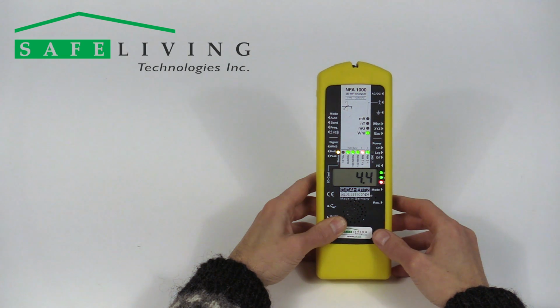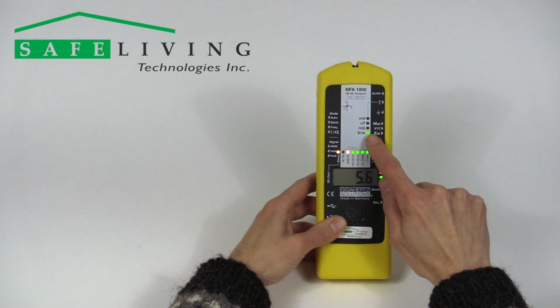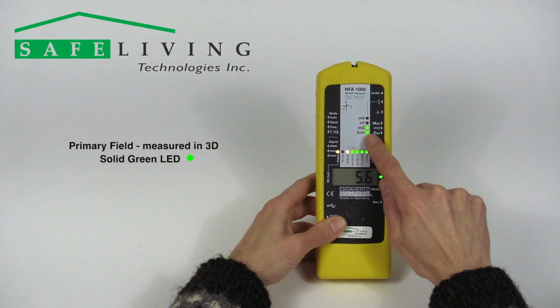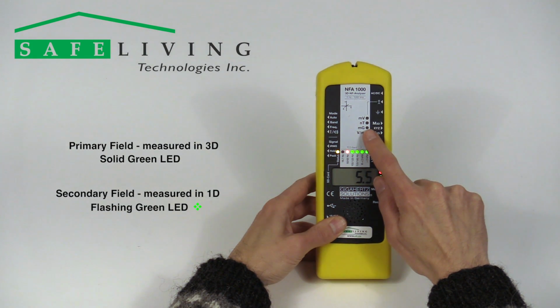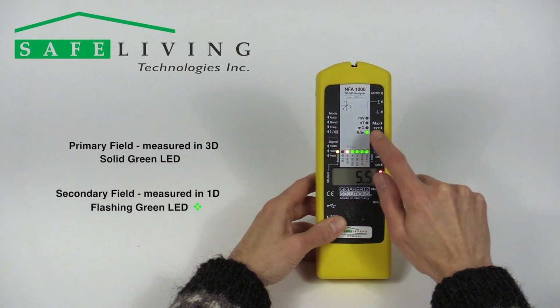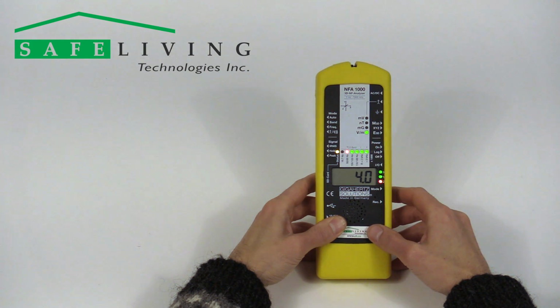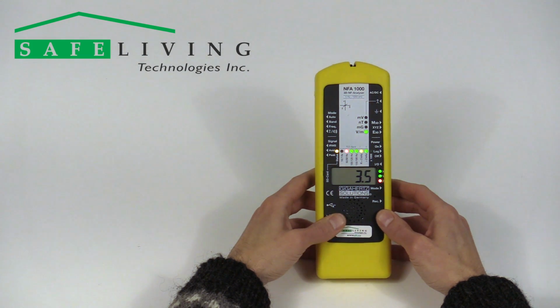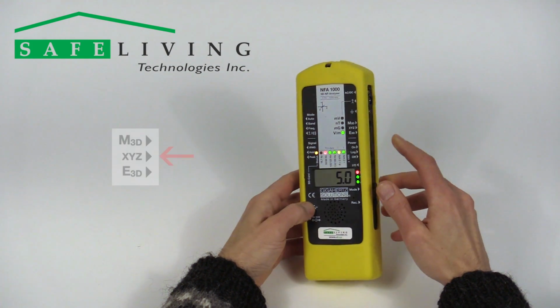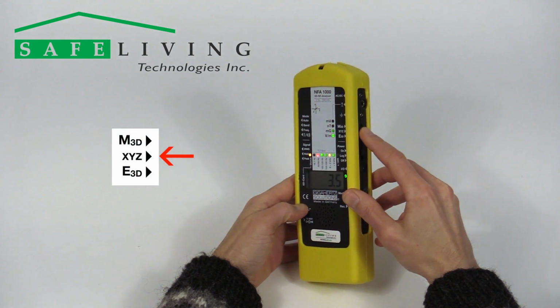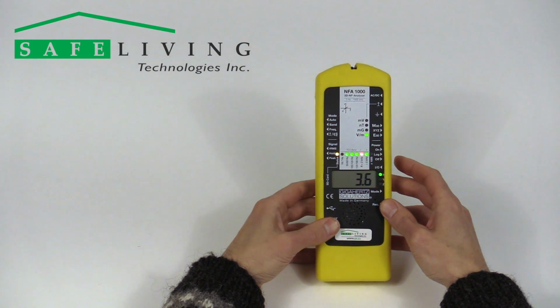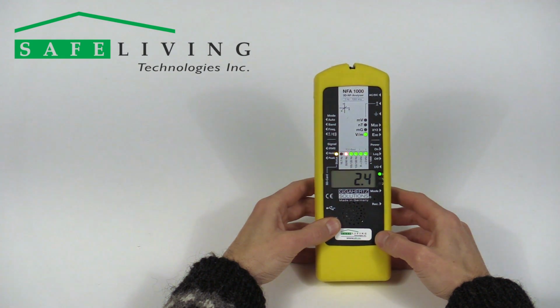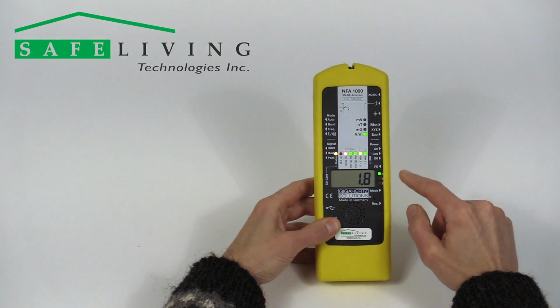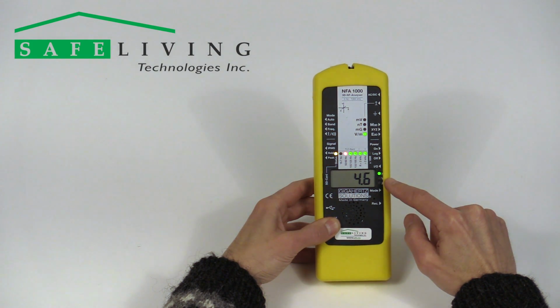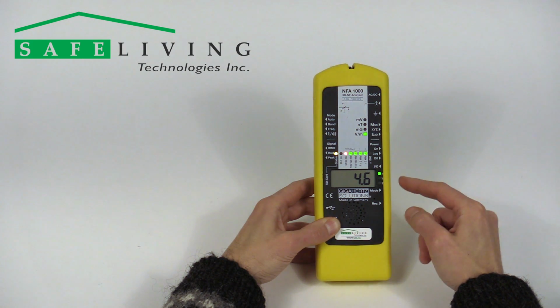The LEDs shown here always indicate how the meter is measuring. A solid green LED shows the primary measurement, which is in 3 dimensions, and a flashing green LED shows the secondary single-axis measurement. If you would like to measure only a single axis at a time, the meter can be changed to single-axis mode by moving this switch to the X, Y, Z position. Now the meter only shows the measured value of each axis that you choose. These LEDs show which axis is currently selected. This can be changed with each press of the mode push button.